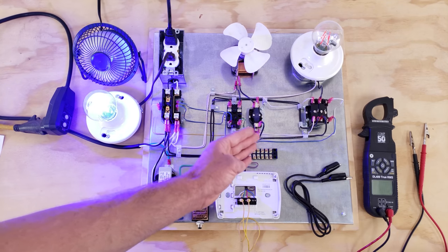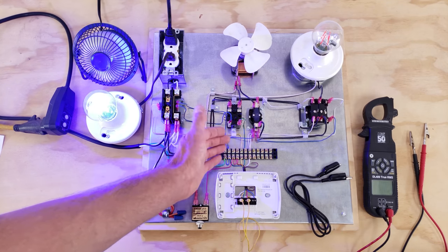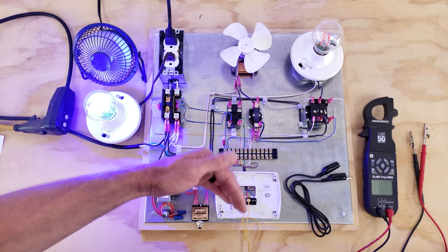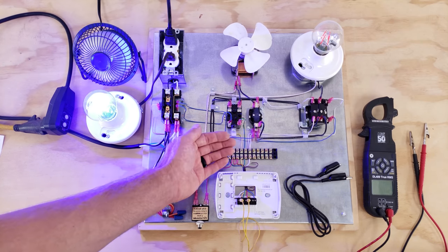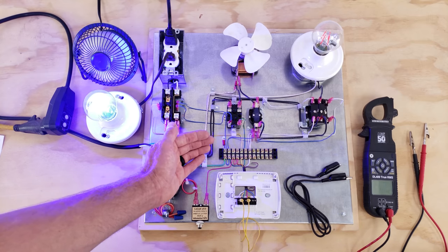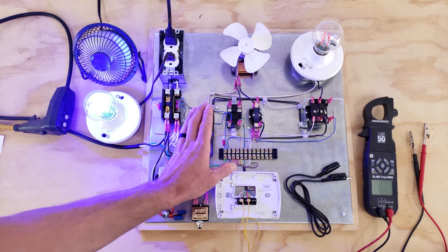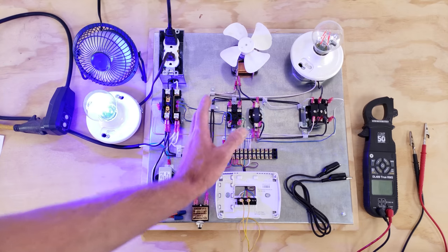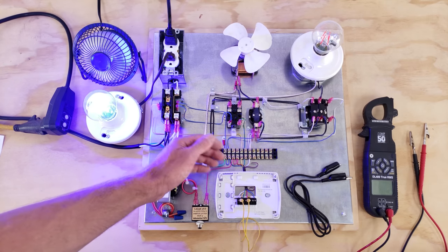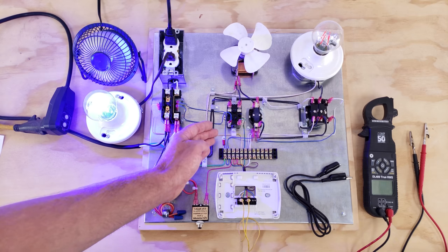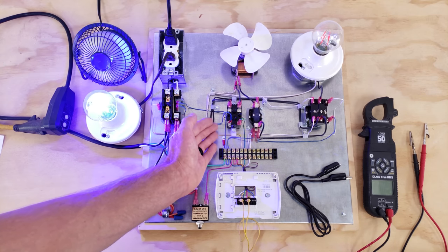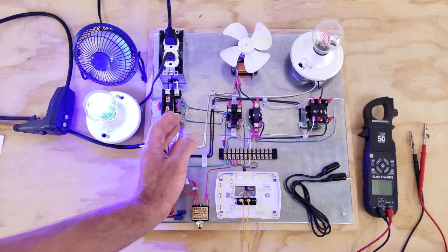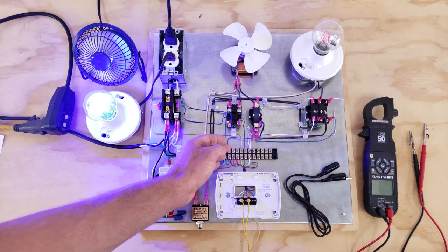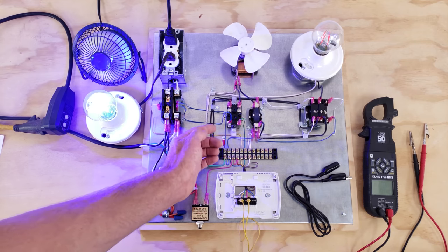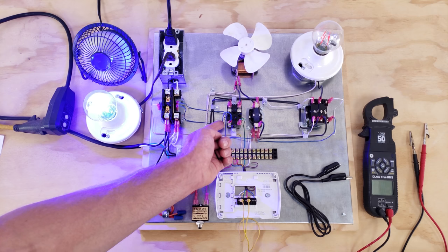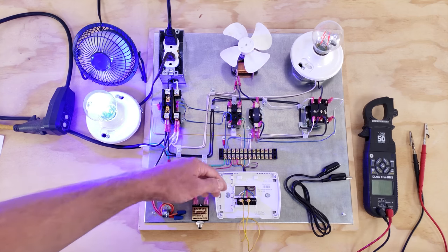Instead of these components right here, you may have a control board at the indoor unit, but in this case, we're just using relays. If you have these relays in your service truck, you can typically get a system up and running. Not necessarily a gas furnace. You don't want to replace that control board with a bunch of relays, but air conditioning systems, you can typically get these systems running. So air handlers, you can rebuild the insides typically with the correct high current contacts for, say, electric strip heaters or things like that. And you have to have a high current fan relay in order for the blower motor to turn on.